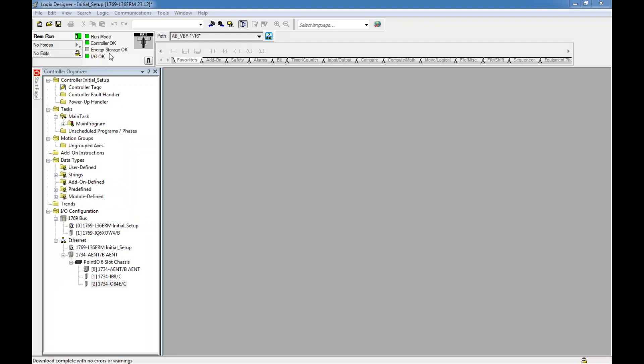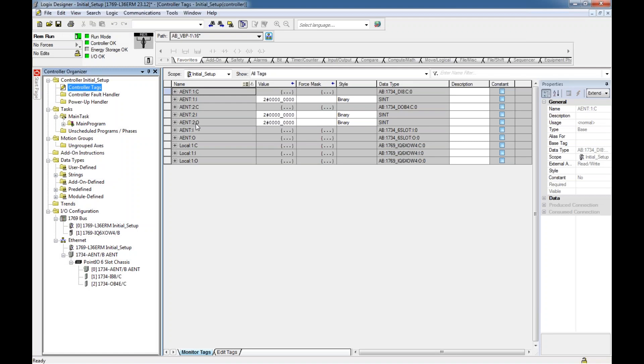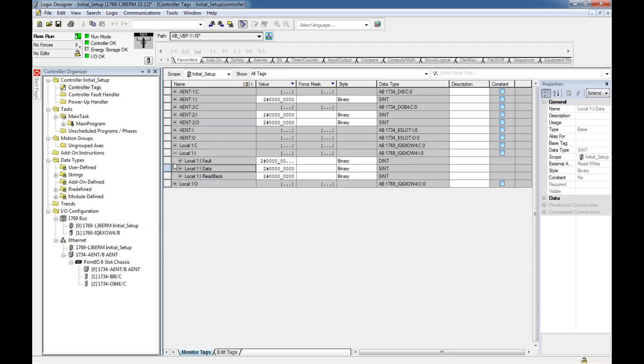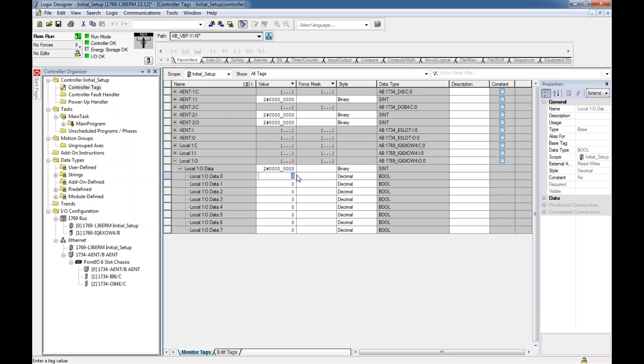If the IP address is wrong or something isn't right, it will say 'IO not responding'. To verify, I go into Controller Tags — here are all my pre-made tags. I open up Local 1 Data and monitor the tags. As I press buttons, you can see Local:1:I.Data.0 turning to a 1. I can also go to my outputs and test them by changing a value to 1. You may hear a click in the background as the outputs turn on.